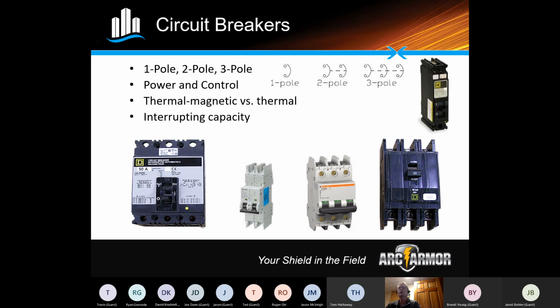Normal circuit breakers come in capacity ratings of 10, 18, 25, 35, 65. They go the whole spectrum, right? If I put that with a starter, just a normal NEMA full voltage non-reversing starter, that starter may only have a 5,000 AIC rating, right? So if you took those two together, you have to take the lowest one. So now I'm at 5,000, right? And if my panel needs to be 10, I can't get there that way. So I have to redesign the panel and use different components.